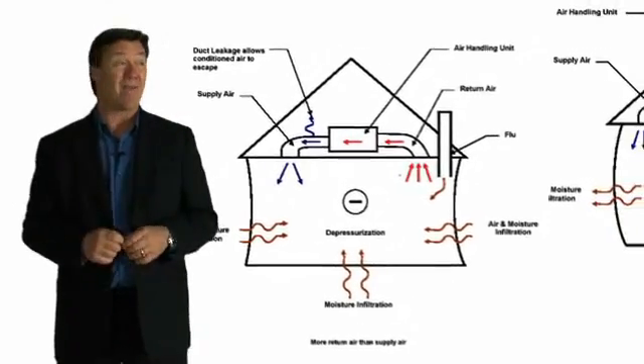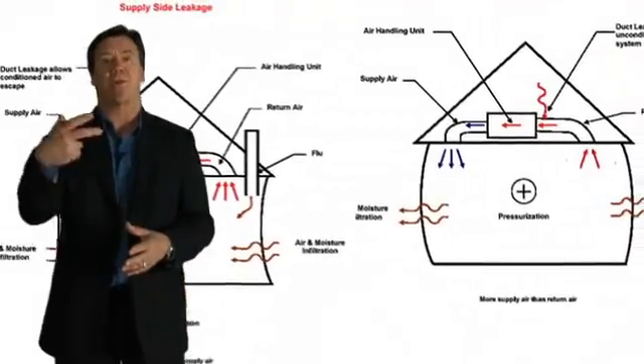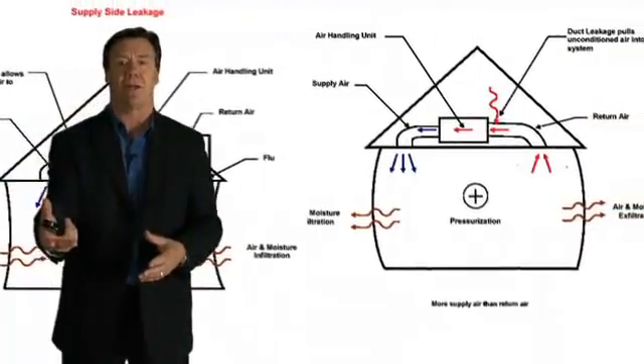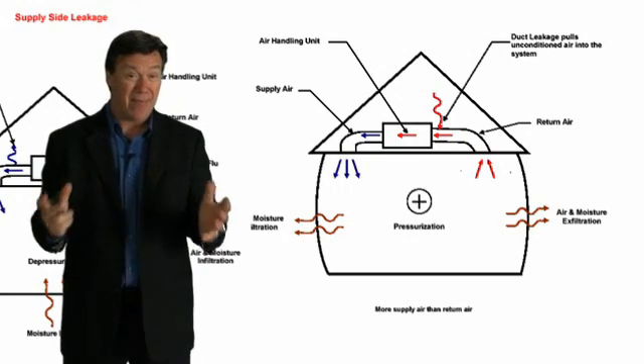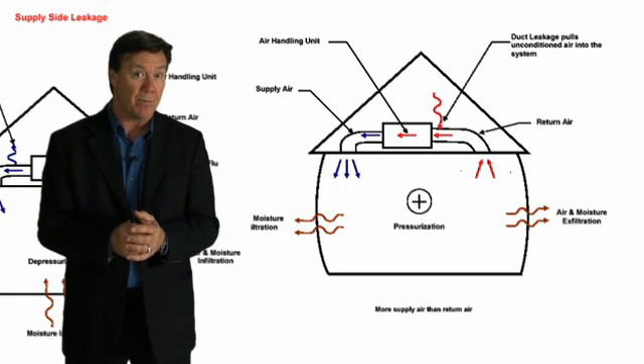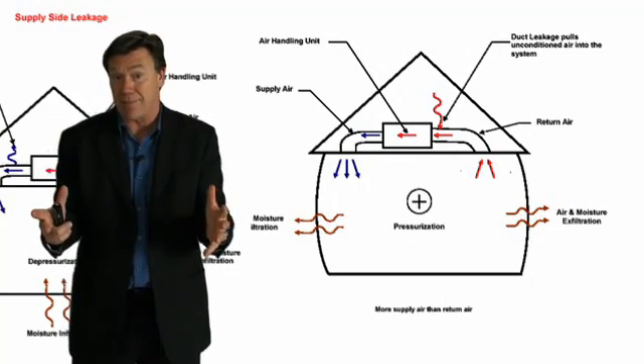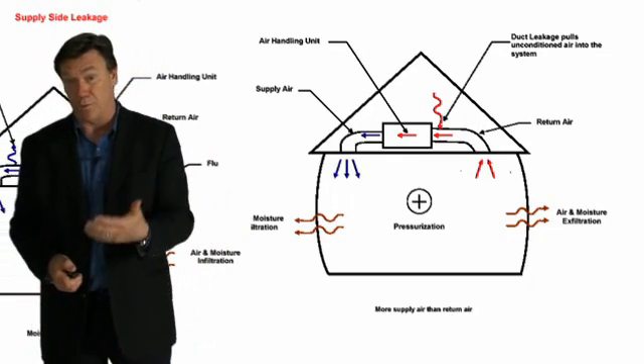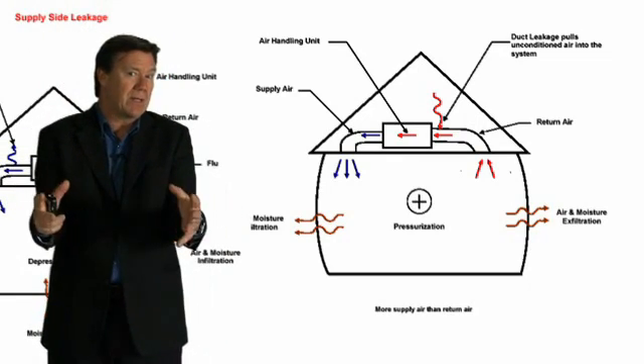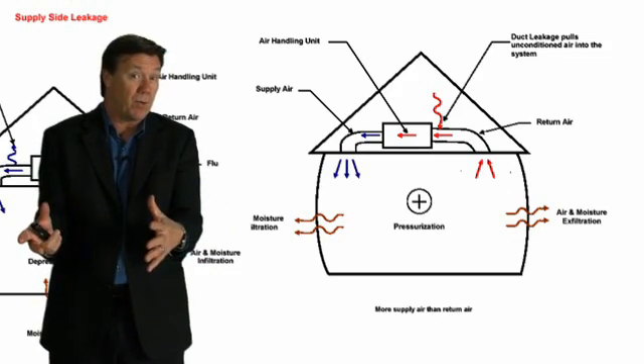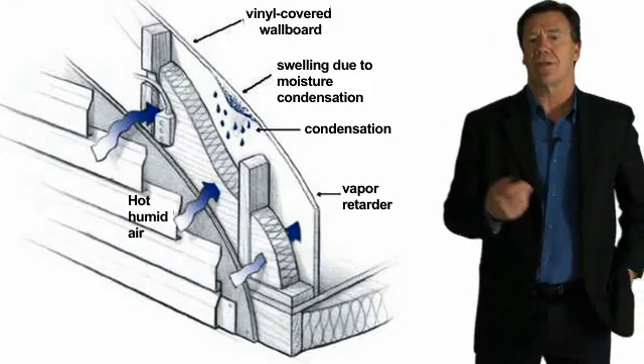Likewise, if we have return air duct leaks located outside the building envelope, just the opposite happens — the home is under a positive pressure. That's a problem in the winter months. Humidified air inside the home is forced out through all the cracks and gaps, and that warm moist air, when it comes in contact with the cold exterior sheathing or components, can condense and lead to mold problems.